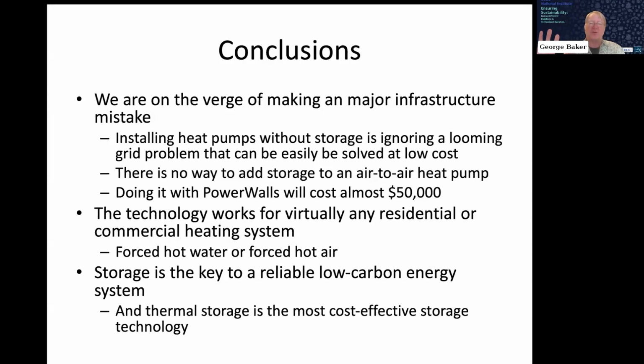Just for comparison, storing 5 hours of heat on a really cold day with 320-gallon tanks of water would cost about $50,000 in chemical batteries — you'd need 4 Powerwalls to do that. Those tanks cost about $1,000 a piece, and installed, we figured the storage system costs about $4,000 in our basements in Maine. It's a substantially cheaper solution than trying to store energy with chemical batteries.